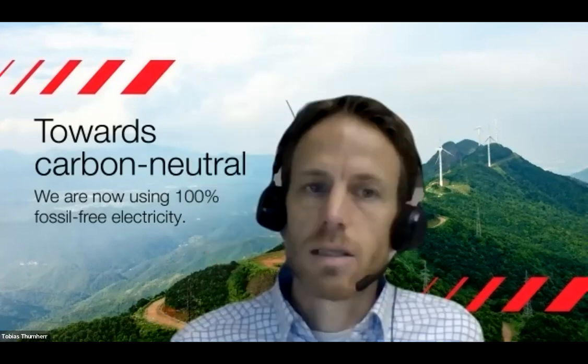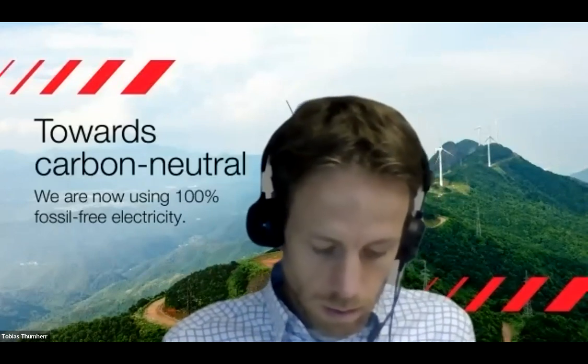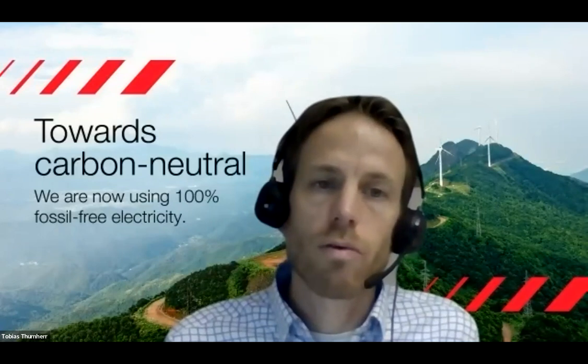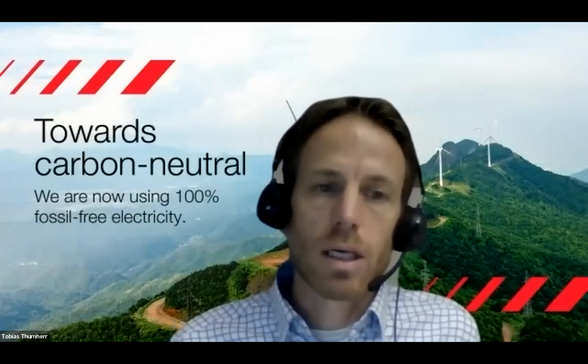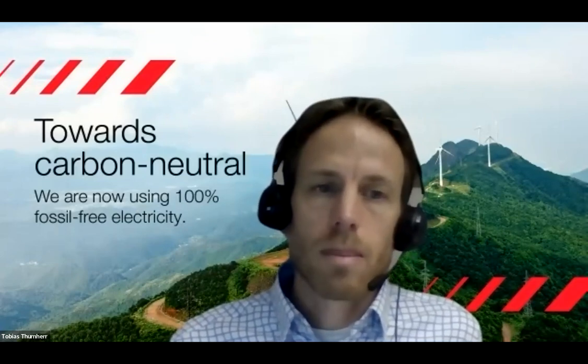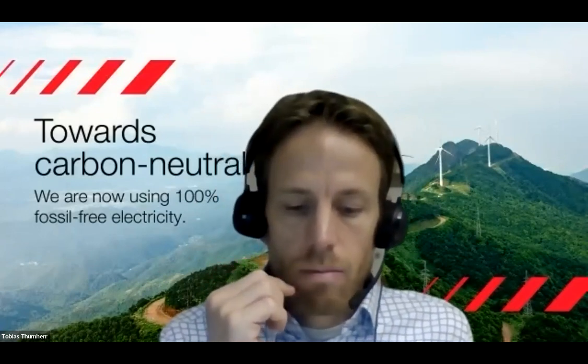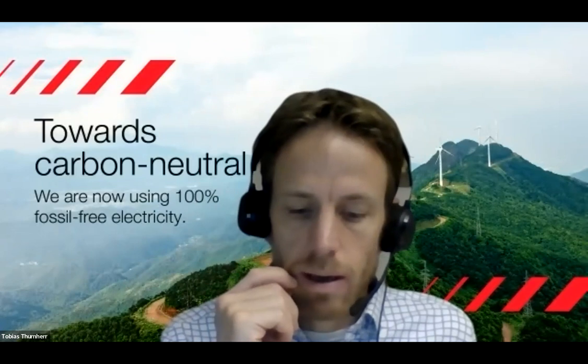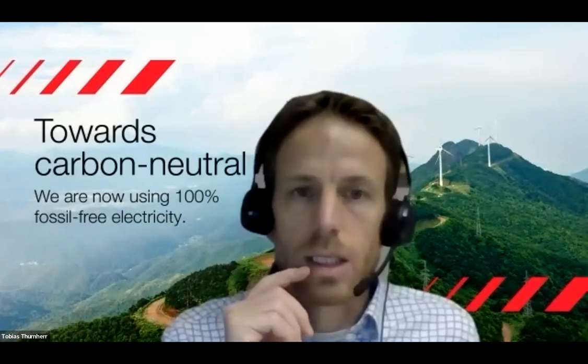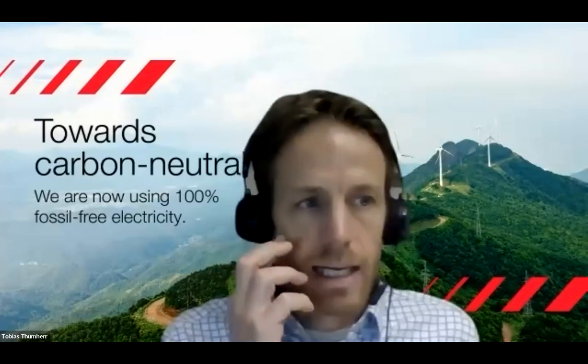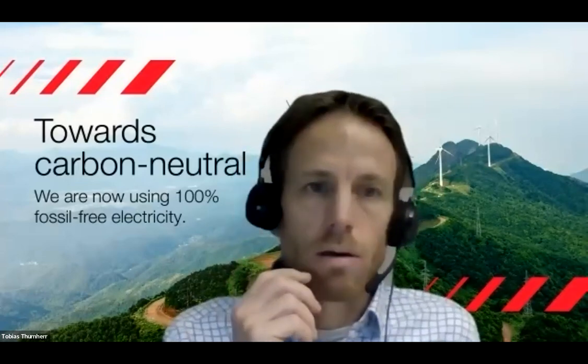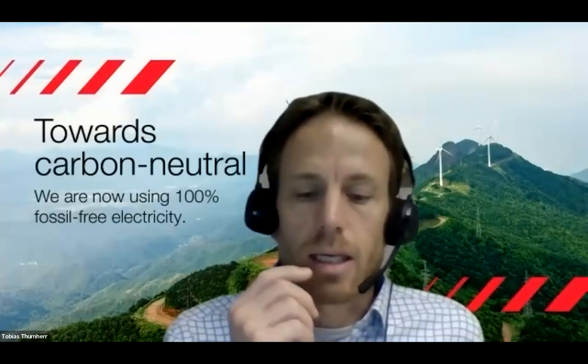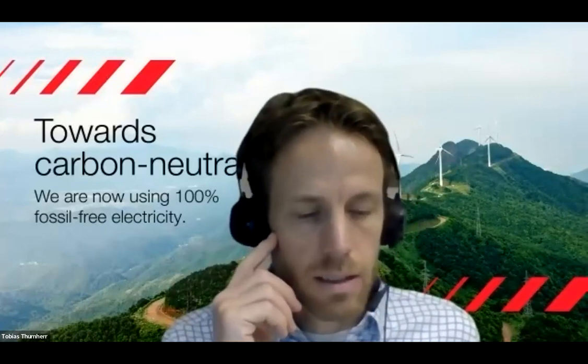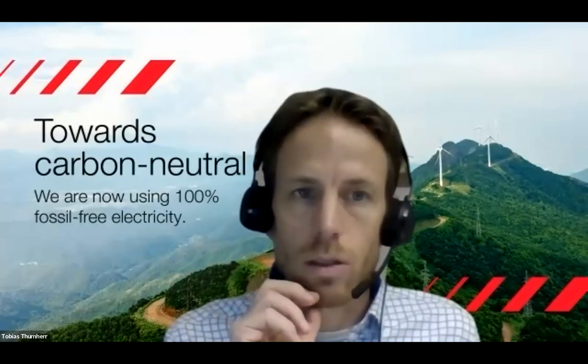Okay, thank you. I think the tests were done on the real-time simulator with a full load. It's very easy to do these tests now. What helps is if you compare the behavior of the fault with no load on the real-time simulator and on the real side, then you can validate the correct behavior of the real-time simulator. But I think it's more complicated to do the tests on site with the full load, and that's probably the reason why it was not done.